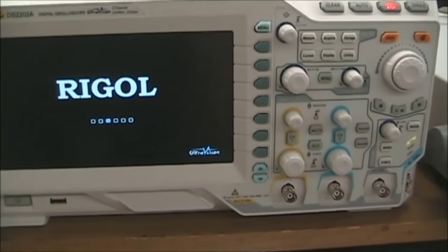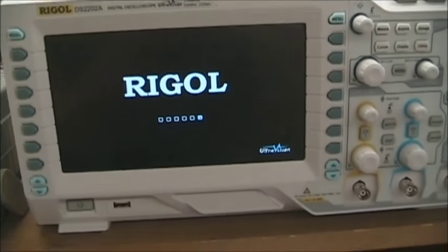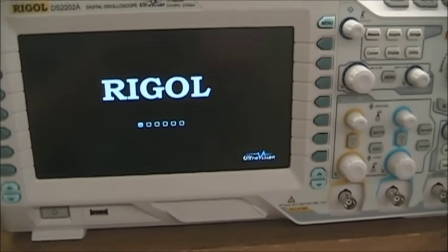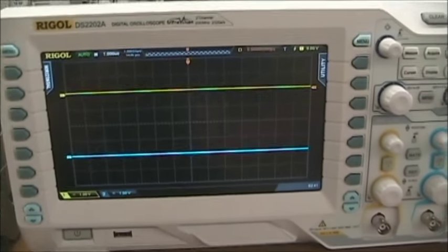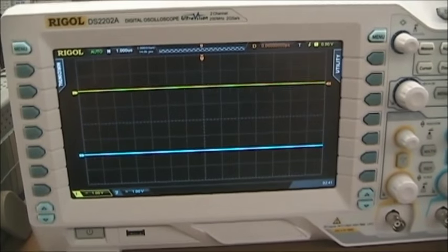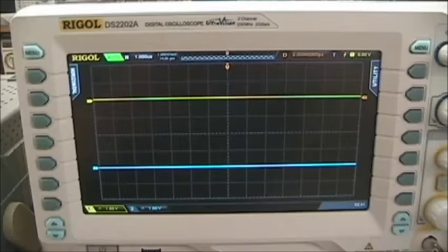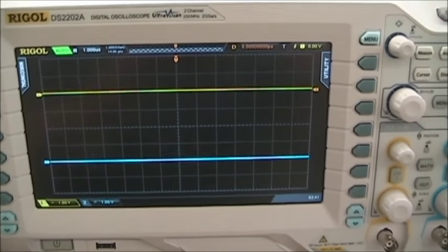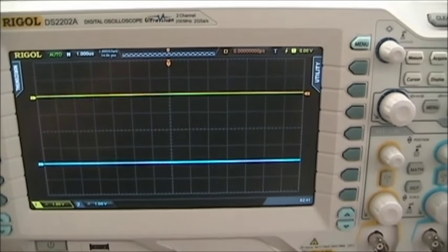These are modern digital instruments, and there's a couple things you need to know about these instruments. One is they can store settings for the users. Now this is both a good and a bad thing. If you're a user that only uses this machine, you can preset values for probes and a variety of things. But as one of many users, you might want to take a few steps ahead of time to make sure that the instrument is in the condition you expect when you come in.